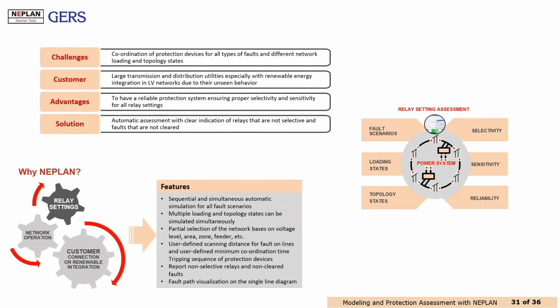The other part that I presented here was the protection assessment. Since we can see that there are many possibilities on the topology states, on the fault scenarios, and the loading states, many possibilities, even the short circuits on the line, they are automated, and NEPLAN will give an indicator about where the protection selectivity fails or not.